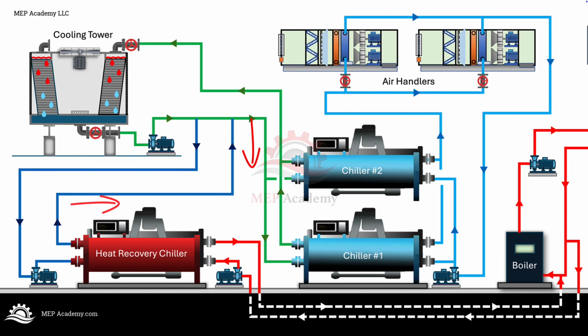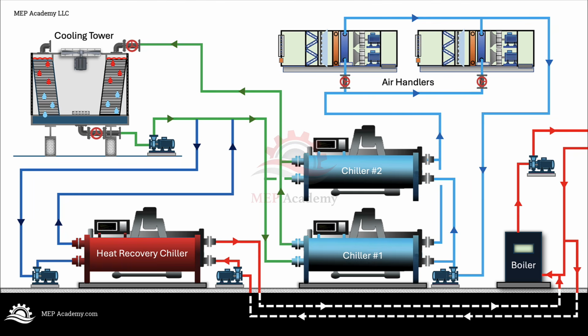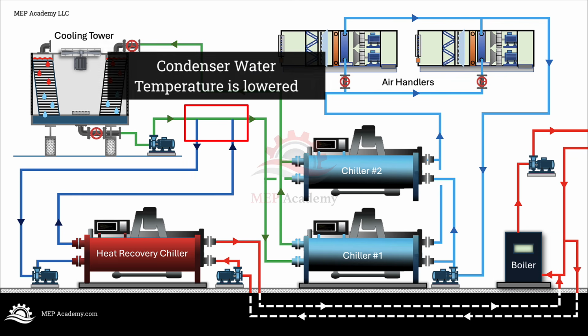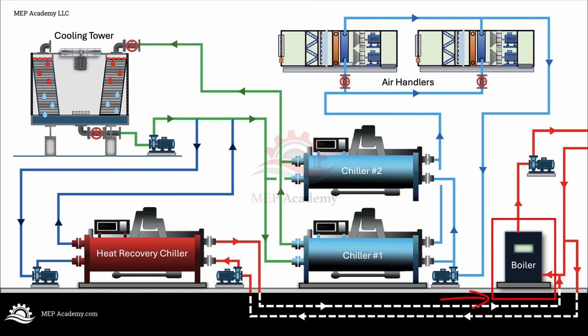From the main chillers' point of view, they are now receiving cooler condenser water. That can reduce compressor lift and improve chiller efficiency. But the heat removed from the condenser water is not wasted. The heat recovery chiller captures that heat and sends it to a useful heating load. For a diagram, picture this system in three sections. The condenser water gives up heat to the heat recovery chiller. The heat recovery chiller sends that recovered heat to the hot water loop. The condenser water continues to the main chillers at a lower temperature. The main chillers operate with cooler condenser water. The heating system receives heat that would otherwise have been rejected outdoors.